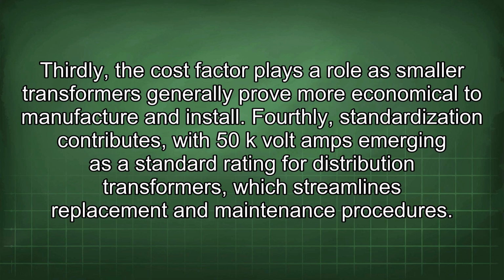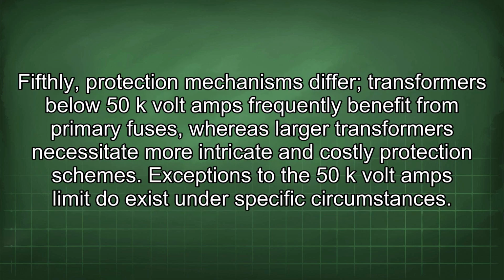Fourthly, standardization contributes, with 50 kVA emerging as a standard rating for distribution transformers, which streamlines replacement and maintenance procedures. Fifthly, protection mechanisms differ. Transformers below 50 kVA frequently benefit from primary fuses, whereas larger transformers necessitate more intricate and costly protection schemes. Exceptions to the 50 kVA limit do exist under specific circumstances.